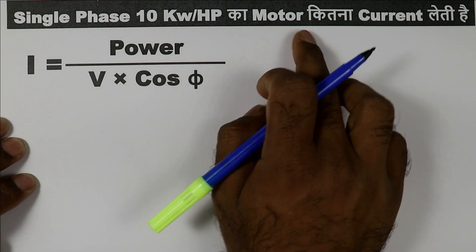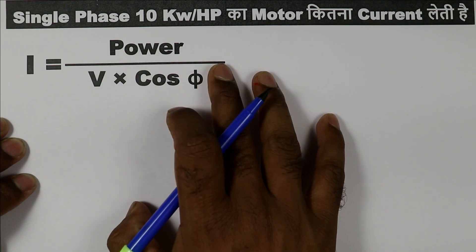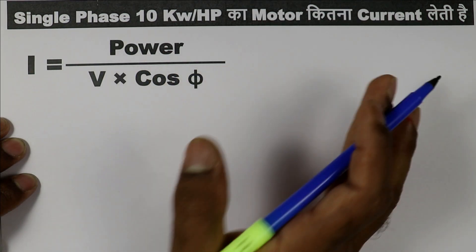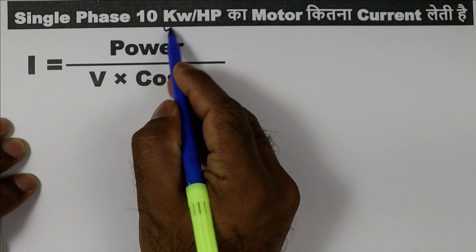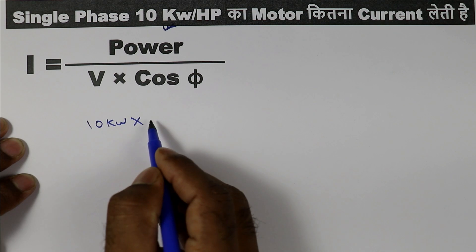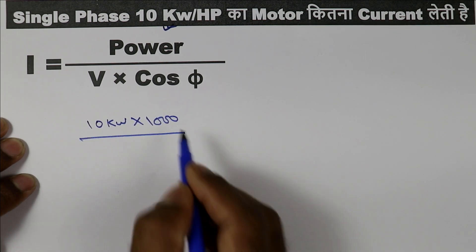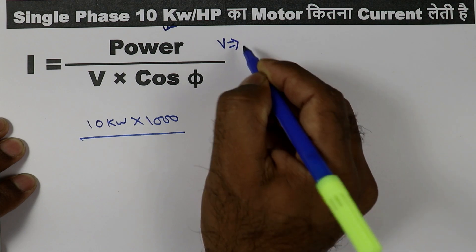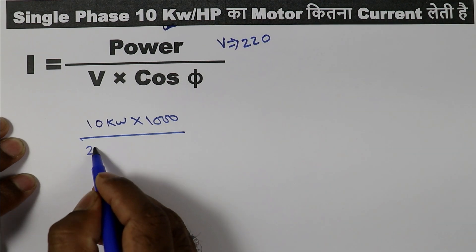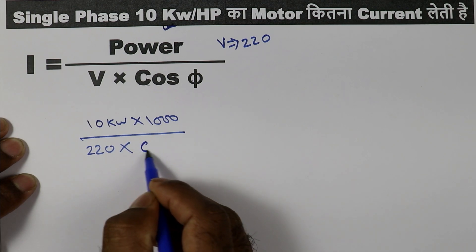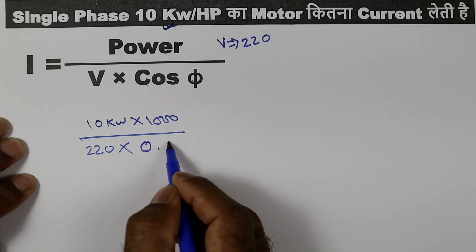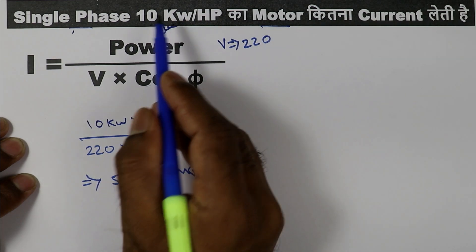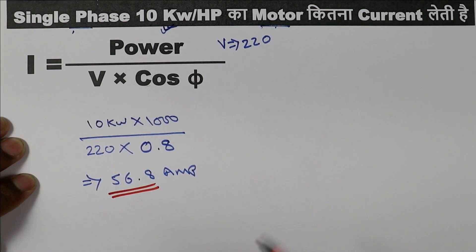Now, if you were asked the current rating for single phase, you have to use a different formula — the same structure but without root 3. For a 10 kilowatt single-phase motor, multiply 10 kW by 1000 to convert to watts, then divide by voltage. If voltage is not given, assume 220V for single phase. Multiply by power factor — assume 0.8 if not given. When you solve this, you get 56.8 ampere as the current rating of a 10 kW single-phase motor.